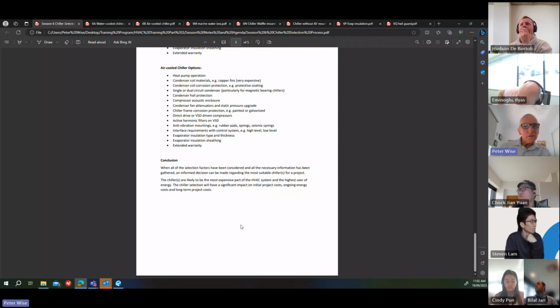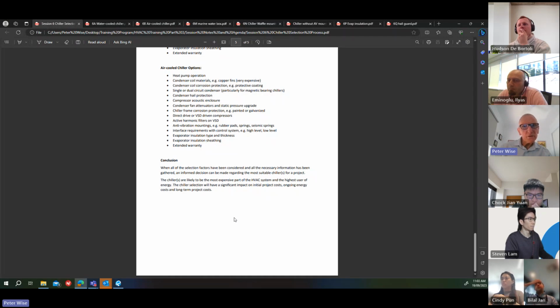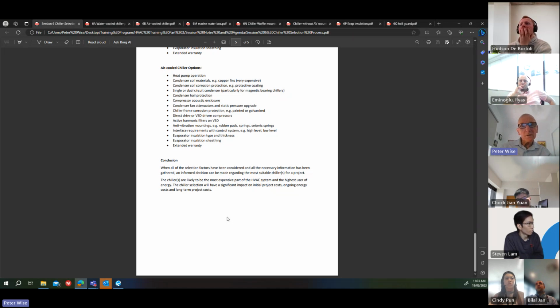It's up to you to protect that from corrosion. Now, you can use a fluid cooler, which is a closed system, and your condenser's fine. But if you're going to use an open system with a cooling tower, then you need to consider corrosion. So they offer that as an option because it's up to you to decide what you need. You can buy a water box with provision to put in a sacrificial anode. That's unusual. Usually they go for cathodic protection, which is the electronic type, and they have to put a few points around the water box for the probes, the sensors to go into, and that can be quite expensive. But I don't think you'll find anyone who offers that as a standard option because it's a very competitive market like everything else. If they keep adding options included in the cost, then they're probably going to miss out on the order. So we have to order those things.